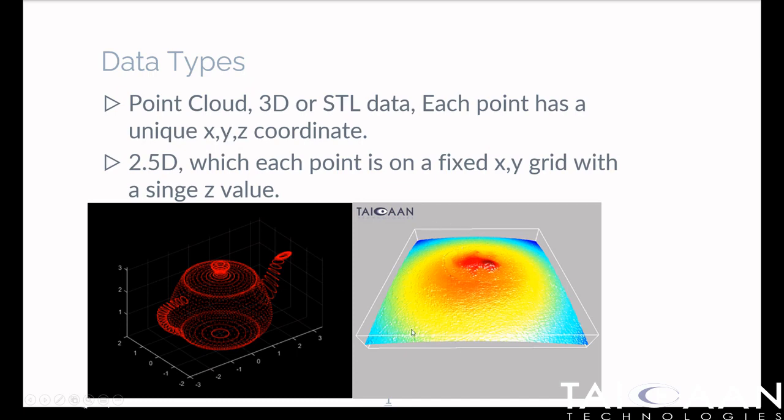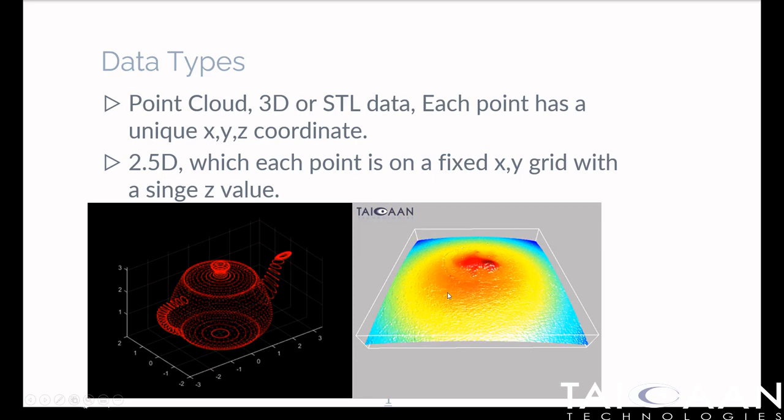The standard format for metrology software is 2.5D, where each point is fixed on an X-Y grid. There's a single value for Z, and that leads to the representation of the surface.